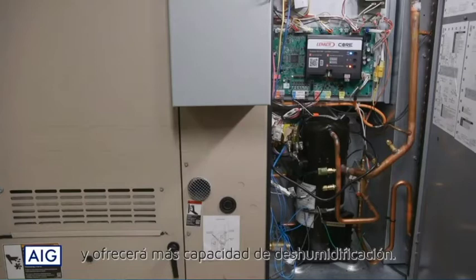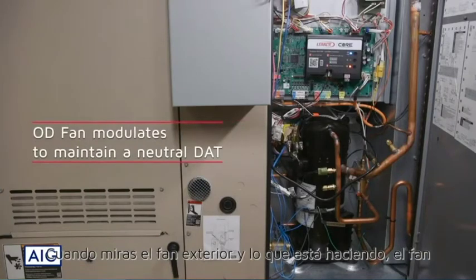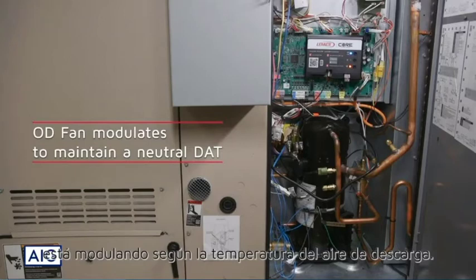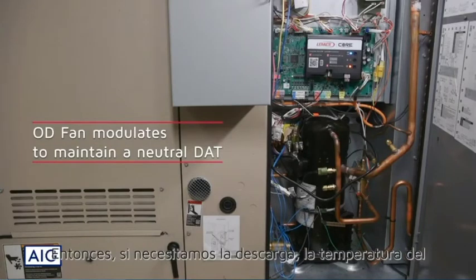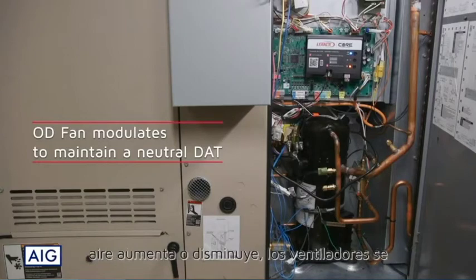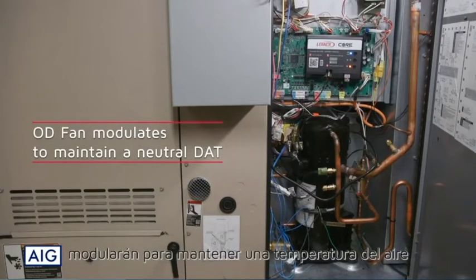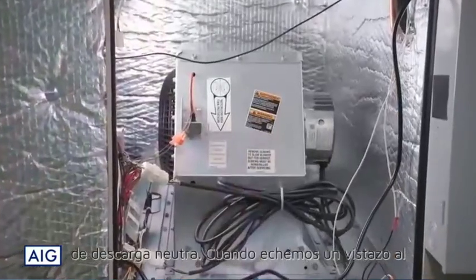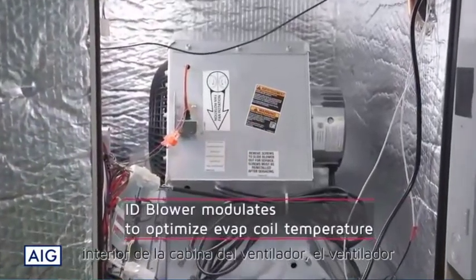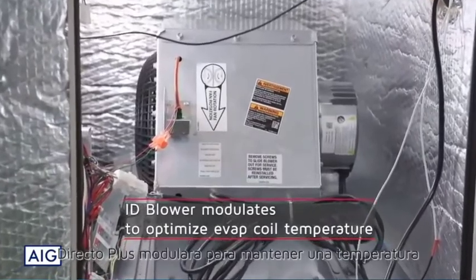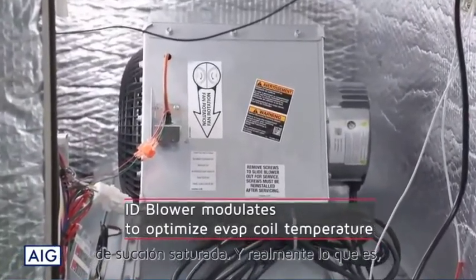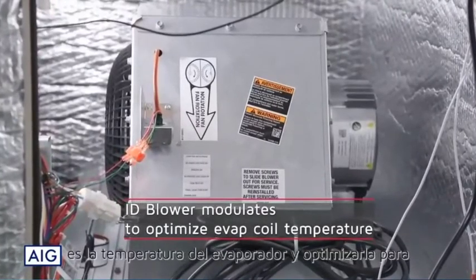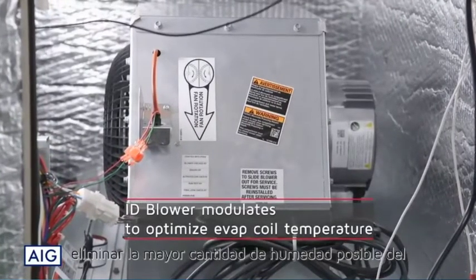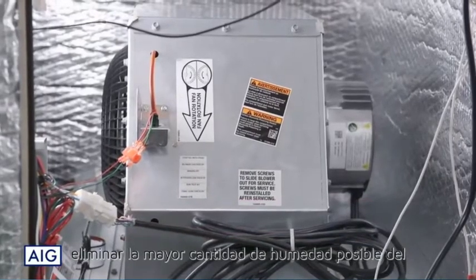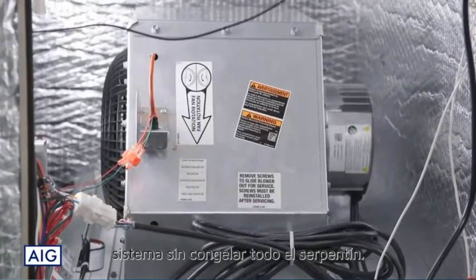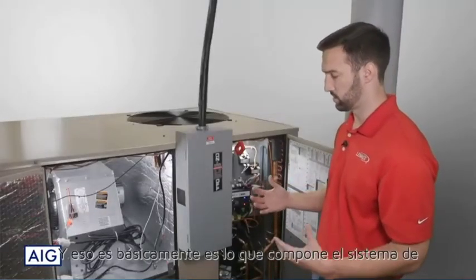When you look at the outdoor fan, it is modulating based on the discharge air temperature. So if we need the discharge air temperature to increase or decrease, the fan will modulate in order to maintain a neutral discharge air temperature. As we take a look inside the blower cabinet, the Direct Plus blower will be modulating to maintain a saturated suction temperature. That's the evaporator coil temperature, and it's optimizing it to remove the most amount of moisture from the system as possible without freezing the indoor coil. And that is basically what makes up the Humiditrol Plus system.